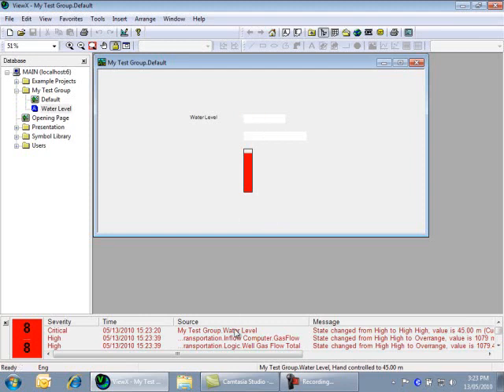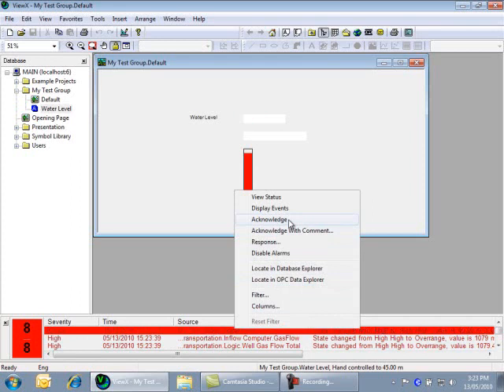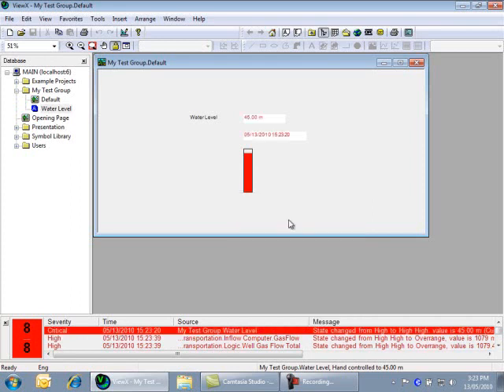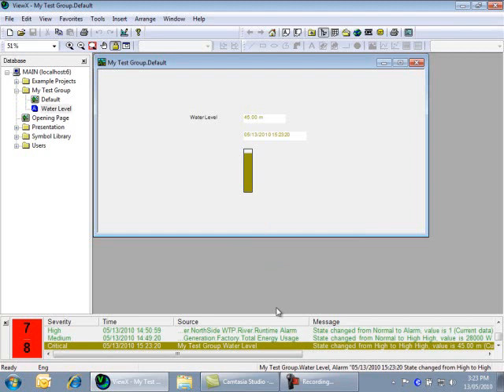Right-click on the point in the alarm banner, and select the Acknowledge option. Note that the point changes to a mustard color. This color means it is acknowledged and uncleared, meaning that an operator has dealt with the alarm, but the alarm condition is still active. If it had cleared before acknowledgement, it would have appeared as flashing green.